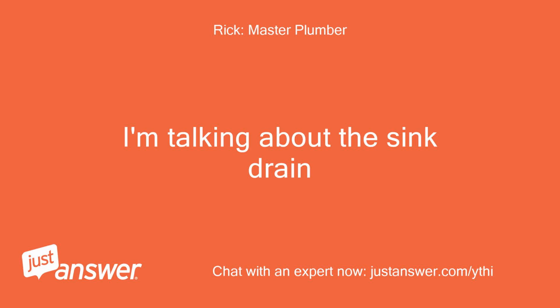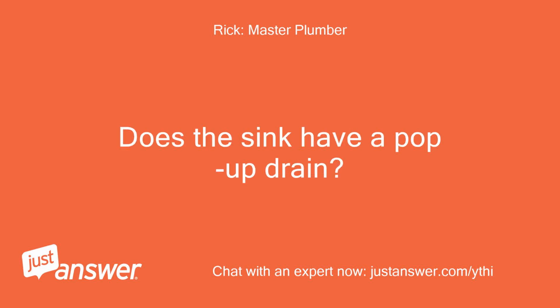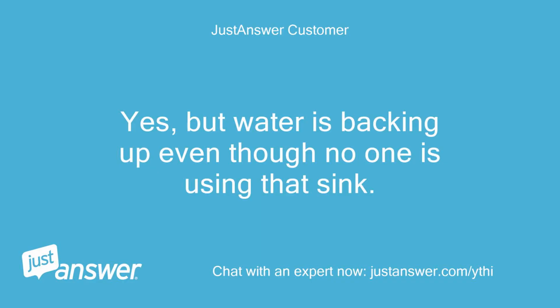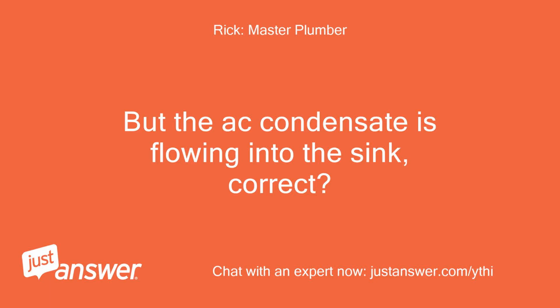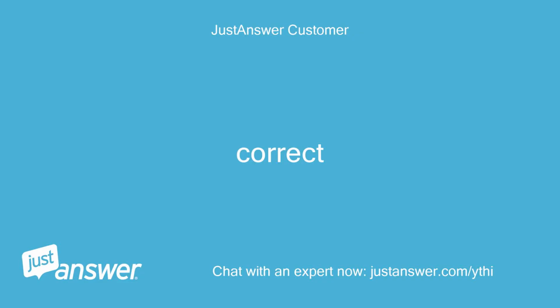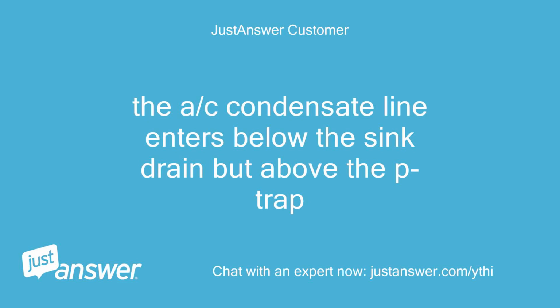I'm talking about the sink drain. Does the sink have a pop-up drain? Yes, but water is backing up even though no one is using that sink. But the AC condensate is flowing into the sink, correct? Correct. The AC condensate line enters below the sink drain but above the P-trap.